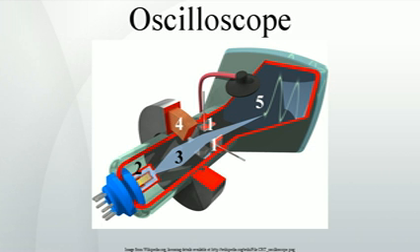Probes. Open wire test leads, flying leads, are likely to pick up interference, so they are not suitable for low-level signals. Furthermore, the leads have a high inductance, so they are not suitable for high frequencies. Using a shielded cable, that is, coaxial cable, is better for low-level signals. Coaxial cable also has lower inductance, but it has higher capacitance.